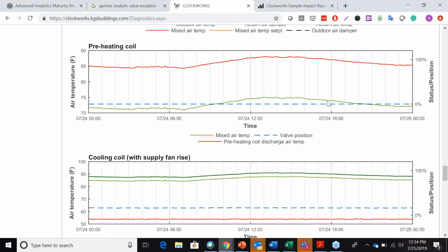So the valve position here is this blue dotted line. That's at 0%. The mixed air temp is in green, and the temperature after the coil here is in red, above. So our air temp is coming up from the mid 70s to the mid 80s. That's that 13-degree heat gain.